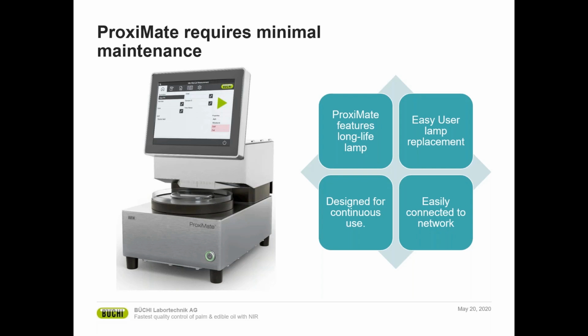ProxiMate features a very long life lamp, so that reduces the amount of user interface that needs with servicing the instrument. And even when the lamp does need replacement, the lamp is easily changed by operators on the ground. The instrument's designed for continuous use. It's designed to be left switched on continuously, 24 hours a day, 7 days a week. So it's always available for operators to maximize the value that you can get from the spectrometer during its time in front of the production environment area.